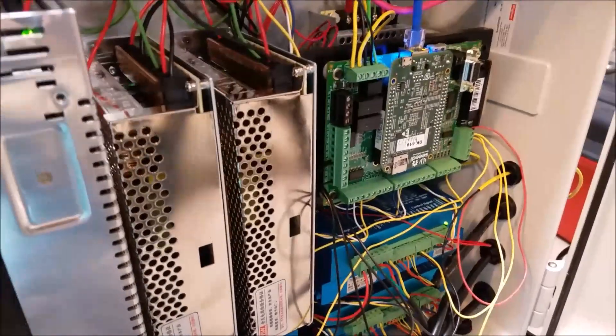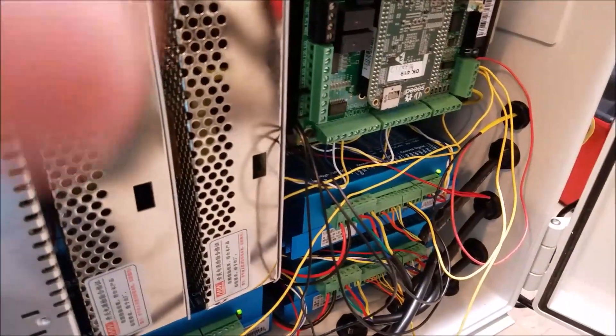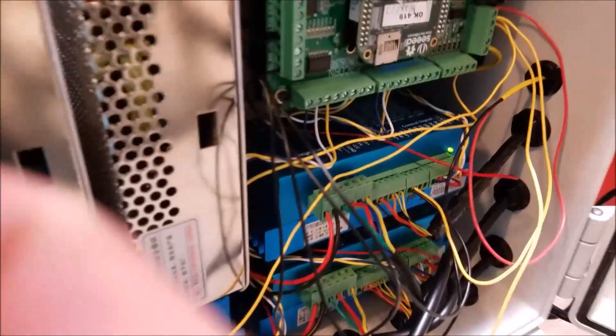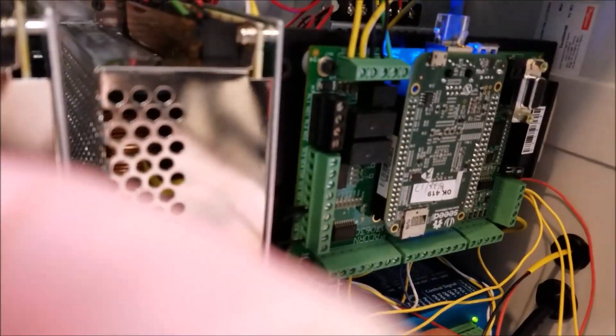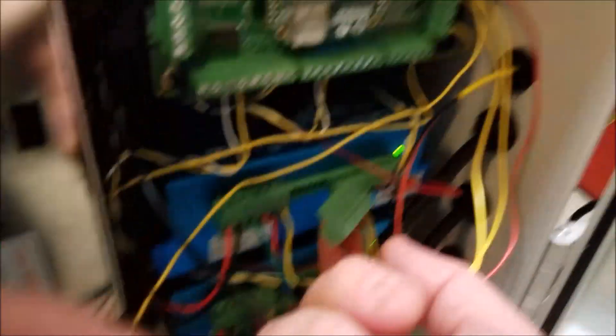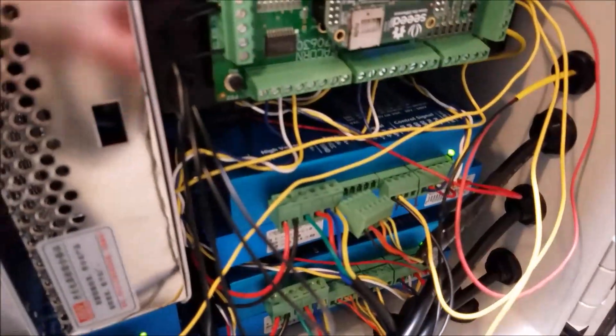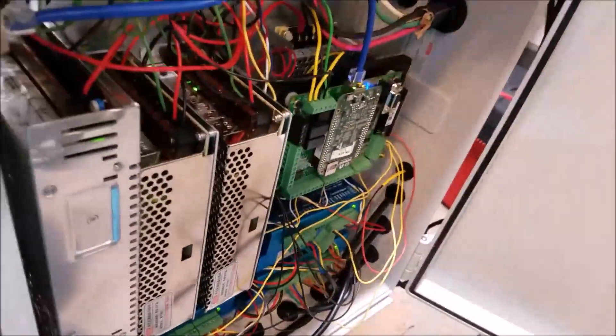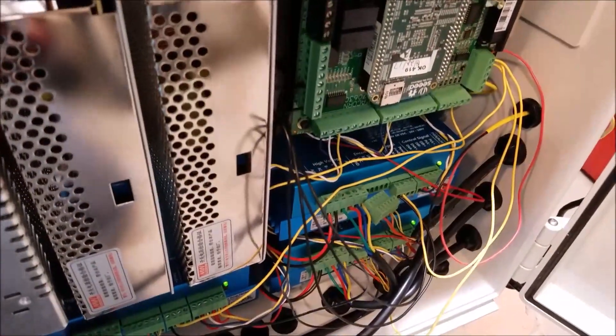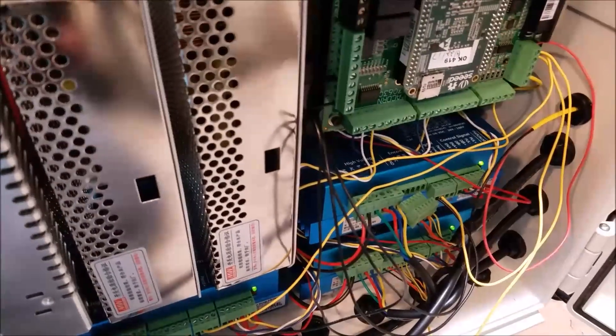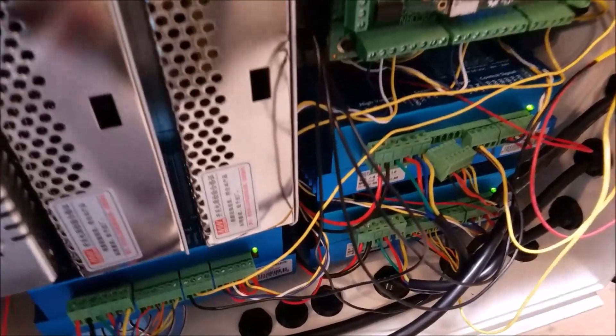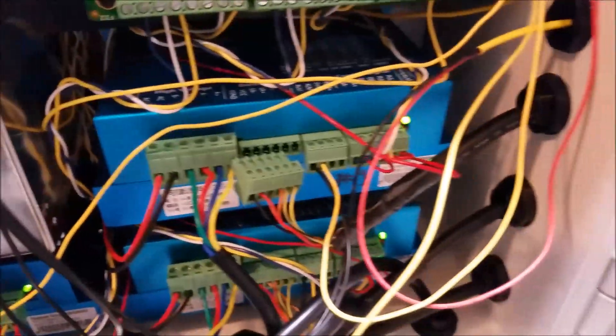So what I'm going to do here is I'm going to simulate an alarm and I am going to do that by very carefully pulling the encoder cable off of my X axis drive. So there we go. I just disconnected the encoder from X axis and what will happen when I do that. So I can move Y, Y is good. I can move Z. Watch what happens when I move X.